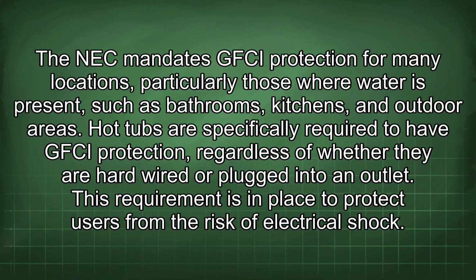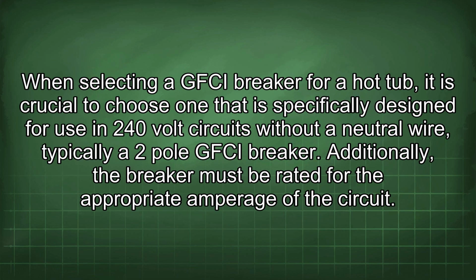The NEC mandates GFCI protection for many locations, particularly those where water is present, such as bathrooms, kitchens, and outdoor areas. Hot tubs are specifically required to have GFCI protection, regardless of whether they are hardwired or plugged into an outlet. This requirement is in place to protect users from the risk of electrical shock. When selecting a GFCI breaker for a hot tub, it is crucial to choose one that is specifically designed for use in 240-volt circuits without a neutral wire, typically a two-pole GFCI breaker.